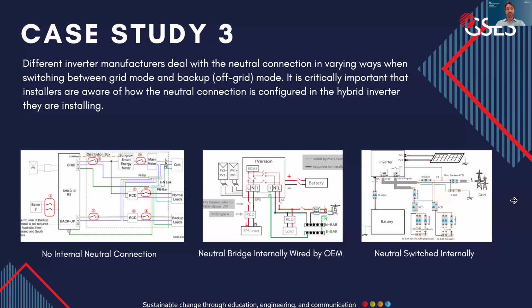In the second example in the middle, a neutral bridge is internally wired by the OEM. In this setup, the original equipment manufacturer has internally bridged the neutral. This can simplify installation, but requires verification within each installation done. In the third example on the right, the neutral is switched internally. This means that the inverter itself manages the switching of the neutral connection. Understanding this functionality is essential for ensuring proper operation in grid tie and backup modes.